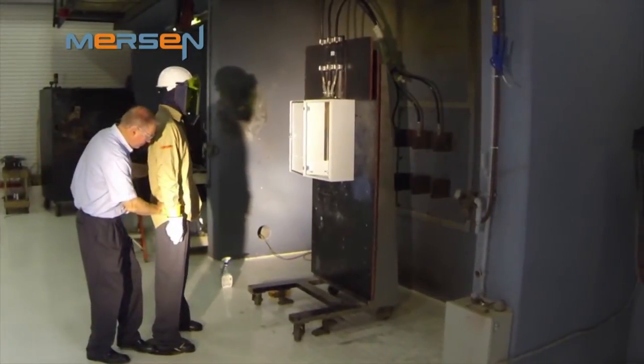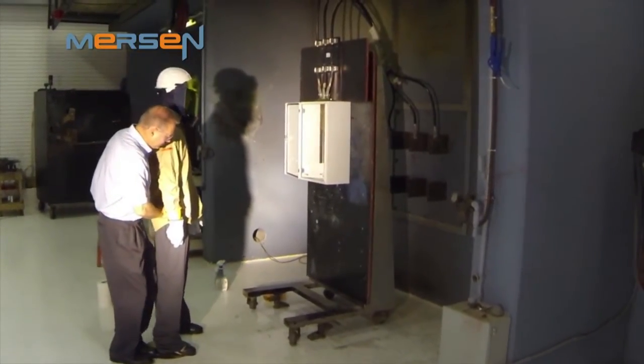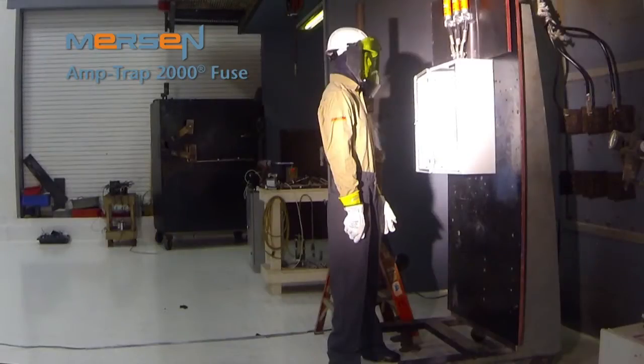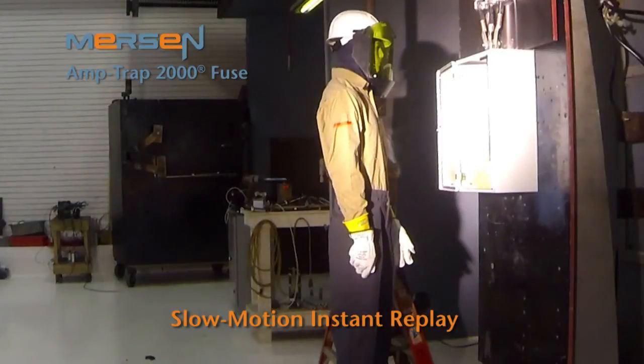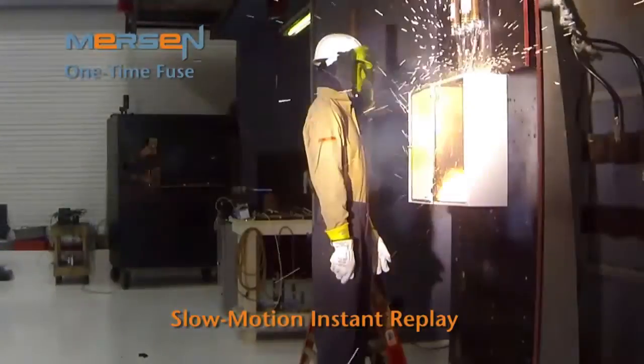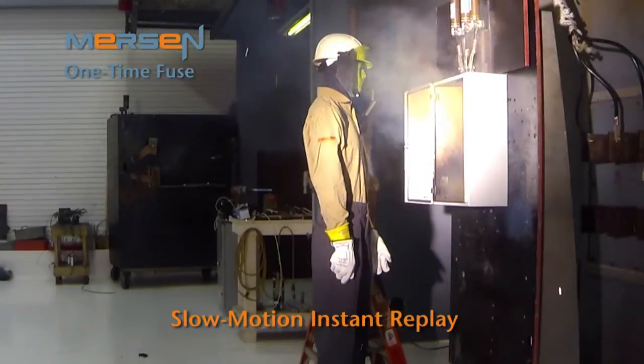We have prepared a mannequin to show the effects on PPE hazard category zero by each fuse type. The first test we will run is using an Amp-Trap 2000 RK1 fuse. You can see that the fuse safely protects the system and person working in the cabinet. There is no noticeable sign of how the fuse opened to protect the system. Now we will perform the same test using a one-time fuse. You will notice that there is more of an impact to the cabinet and the level of energy the worker is exposed to as a result of the fuse's opening.